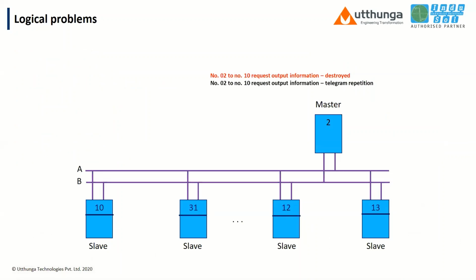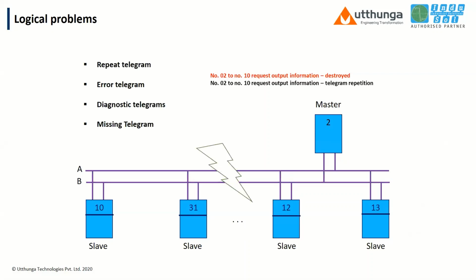Then what are the logical problems? Here is an example: the master is requesting slave number 10, and suddenly the data is getting corrupted. For example, what is a repeat telegram? The master is asking slave number 10, how are you? Slave number 10 is not responding back. Then what will the master do? The master will ask again, how are you? That is a repeat telegram. That is a deviation from the standard. That should not happen in the network, and should not be allowed in the network. This may cause intermittent failures or tripping in the network.